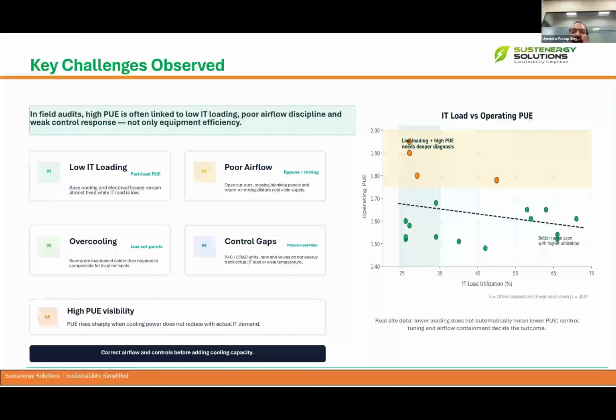So we need to understand the key challenges observed in the cooling. There are 3-4 levers in that. As we discussed, first is low IT loading. Based on the studies done in data centers, we observed that most of the data centers in India are operating between 25 to 65% loading. And some data centers we found are even operating at 6-7% loading. They are newly installed data centers, not fully operational. So that's why the loading is very low, but the PUE is very high. In their case, we found a PUE of 2.1, 2.2, up to 2.4 also. So low IT loading is one of the levers which is affecting the efficiency of the cooling.